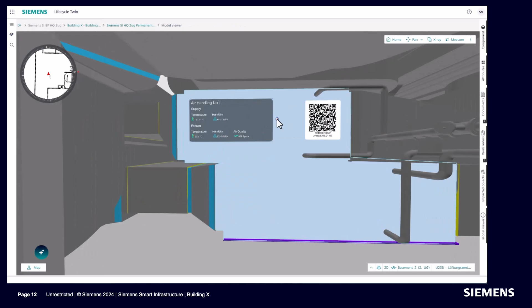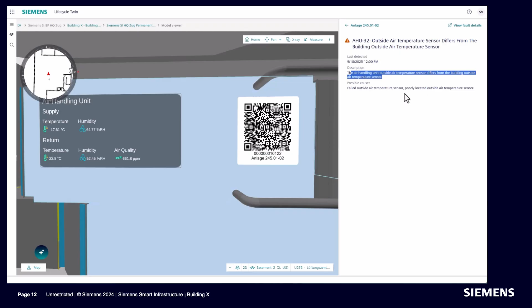I see all the different faults that are registered. These faults are triggered by different rules configured on the system. So I see the outside air temperature has a problem between the building outside air temperature and the one monitored by the AHU. I check the description, I check the possible causes, I check when this was last detected. I could go through each of the faults and check the problems.